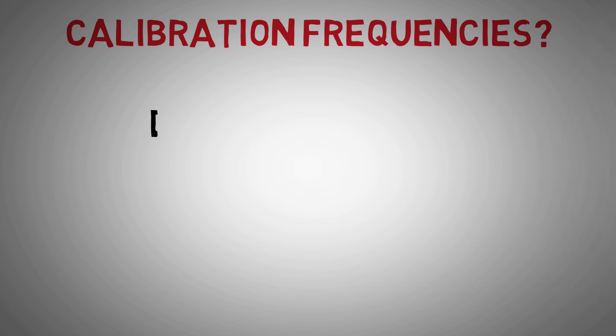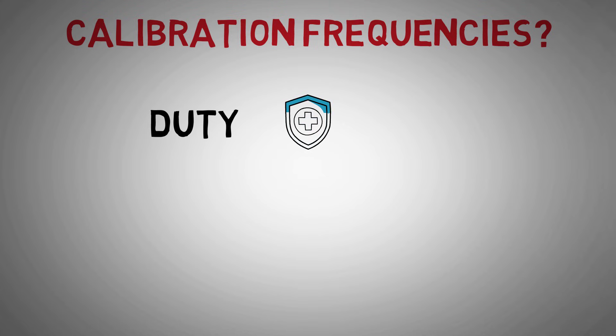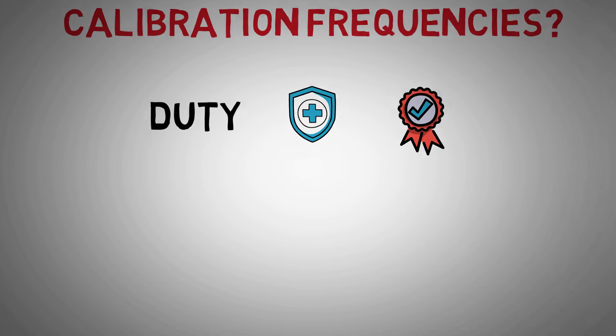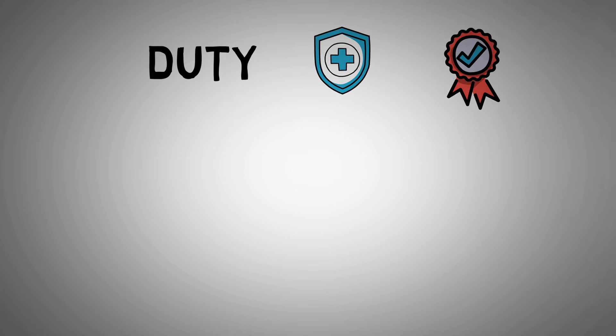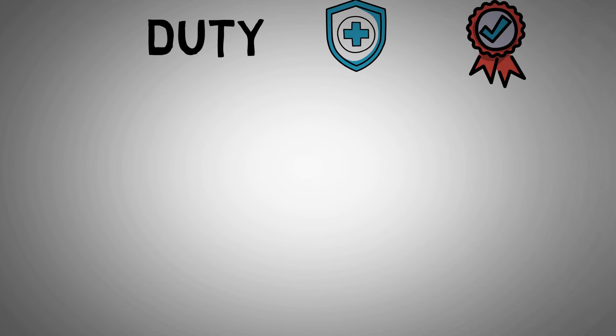So, what determines how often we calibrate an instrument? Duty: if a transmitter's accuracy is safety and quality critical, it might be calibrated monthly. If it is just giving supplementary information, it might only be calibrated every two years.